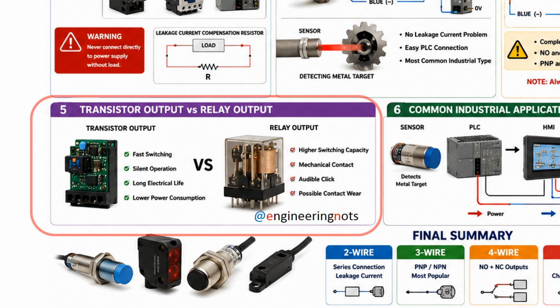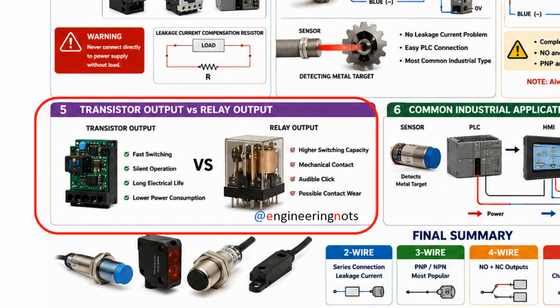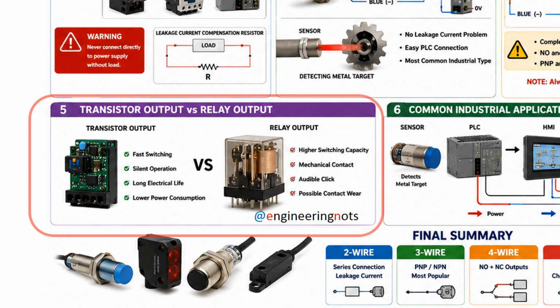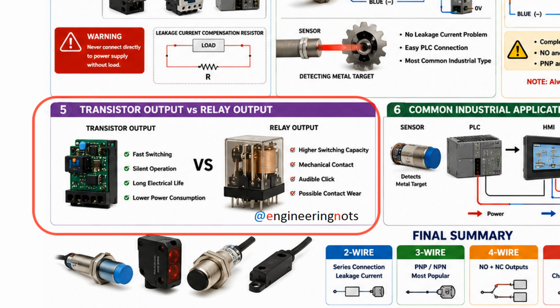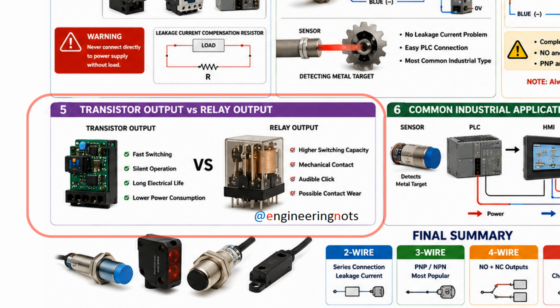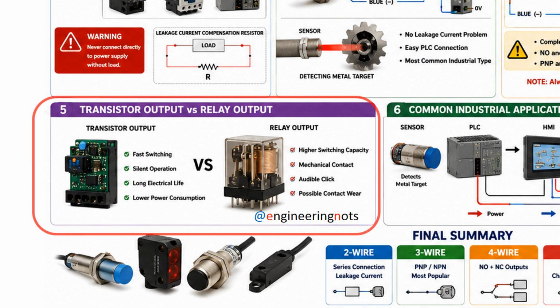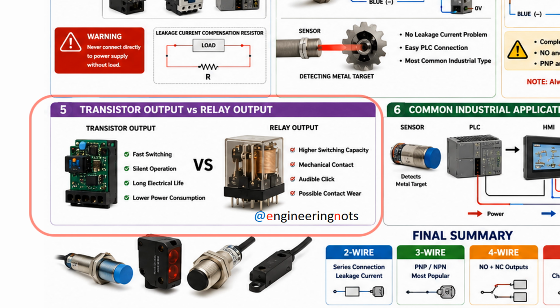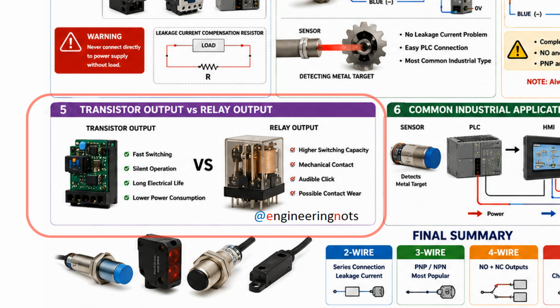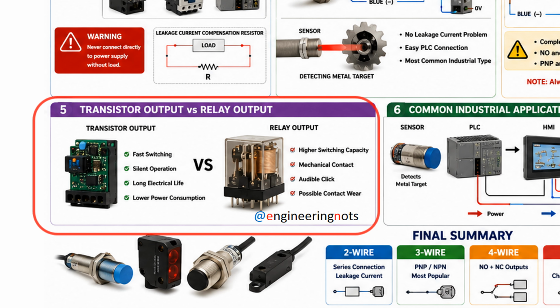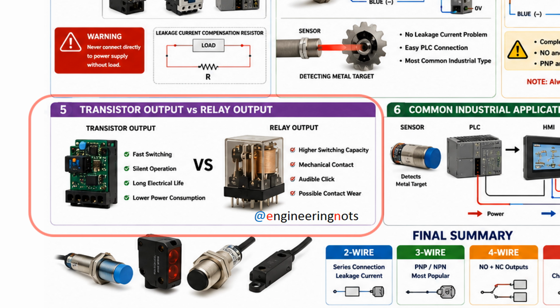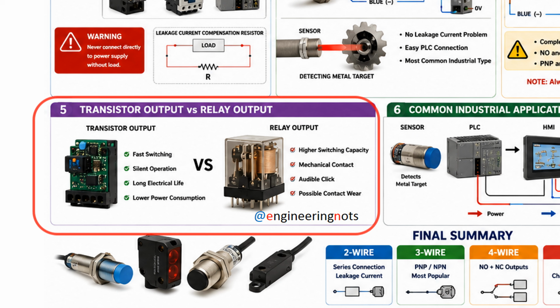Relay output versus transistor output. Transistor output. Very fast operation. No switching noise. Very long service life. Relay output. Higher load handling capability. Greater flexibility. Can switch both AC and DC circuits. However, it operates more slowly. It produces an audible switching sound. And it has mechanical wear over time.